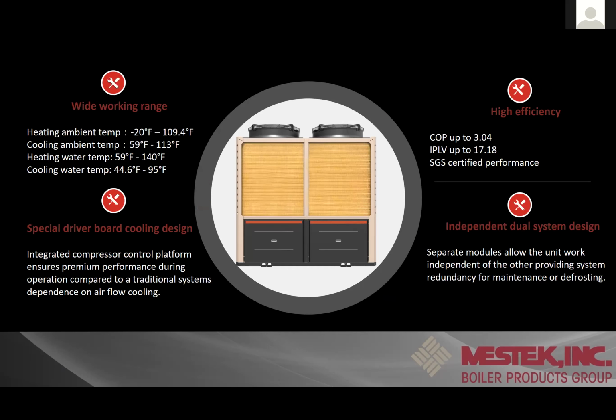This is somewhat redundant on what I already said, but again, on the heating ambient temp. If we're doing heating with this product, -20 to 109 degrees Fahrenheit. Cooling ambient, we can go down to 59 degrees without a parameter change. If we did want to do low ambient cooling all the time, we can go down to 5 degrees if needed. Water temps, as far as heating, say this was being used for like a process heat type thing. We can heat water from 59 to 140 degrees. And then we can also cool water from 44.6 to 95 degrees. So there are some options there.